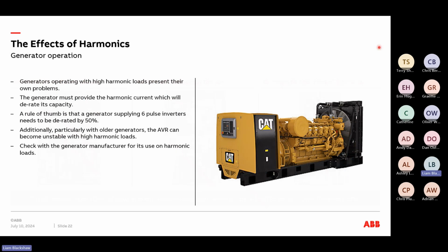But it's also worth noting, when we look at harmonics and generator operation, if we've got a system that maybe has a backup generator on there, and it has high harmonic loads present, then generating or operating generators with that high harmonic load presents its own problems, where in some cases the generator must be able to handle that harmonic current, which will derate its capacity.